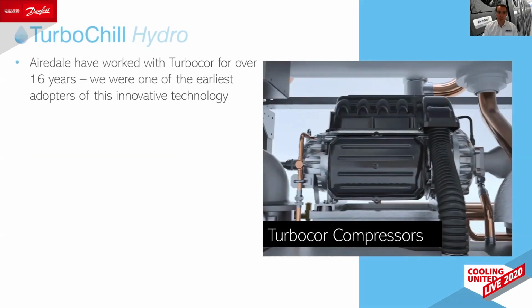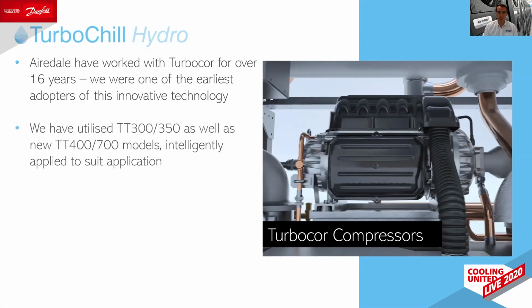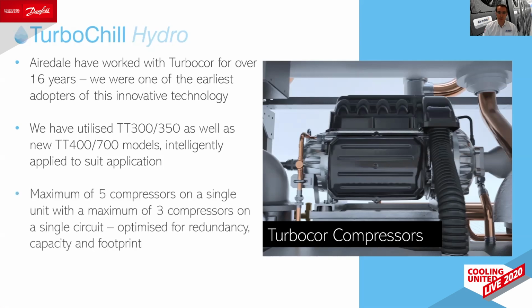Airedale have worked with Turbocor for over 16 years. We were one of the early adopters of this innovative technology. We've optimised for redundancy, capacity and footprint. Turbocor compressors are oil-free, and as such, system performance does not degrade over time. And due to the compact size of the compressor, it offers maintenance benefits. We've utilised the TT300 and 350 compressors as well as the newer TT400 and 700 models, intelligently applied to suit the application. We offer a maximum of 5 compressors on a single unit, with a maximum of 3 compressors on a single circuit, optimised for redundancy, capacity and footprint.